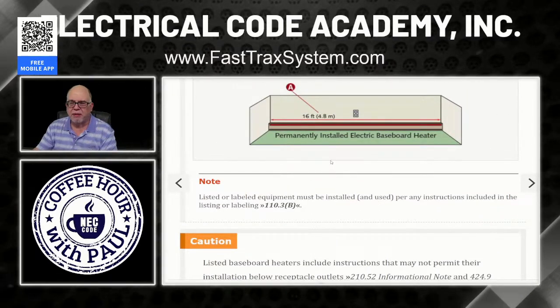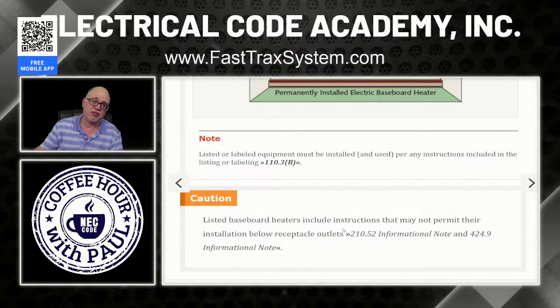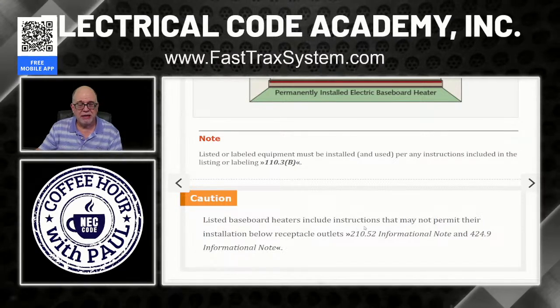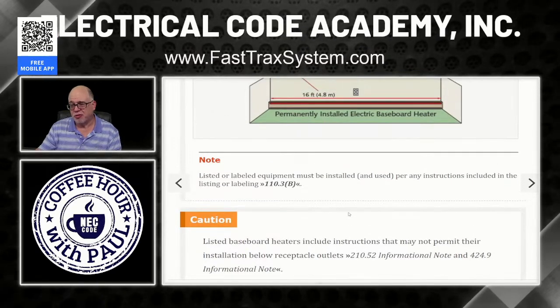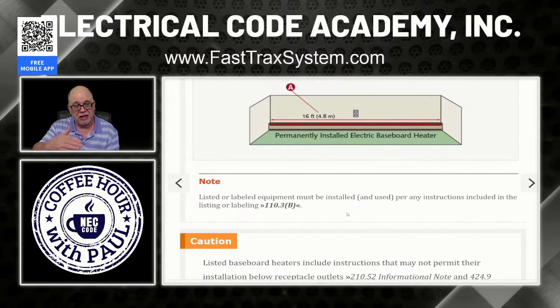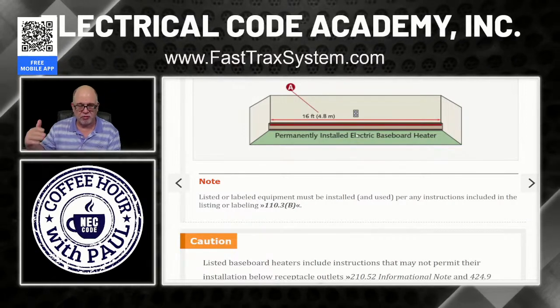Also remember, this typically applies to electric baseboards. You're typically not going to find these instructions for gas type of baseboards. So again, can they be above a gas baseboard heater? Yeah. Code doesn't say anything against it. You still got to look at the manufacturer's instructions, but I can tell you most of the ones that I've seen when it comes to electric baseboards will say not to put the baseboard below a receptacle. Okay. And they do offer some other options in order to do it.